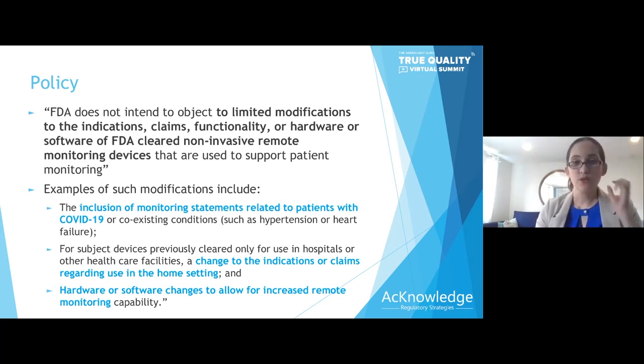If the subject device is previously cleared and only for hospital use, FDA is also interested in allowing—again, they do not intend to object—if you plan to change the indications for use in a home setting. This is really exciting for regulators like me, because if you know what it takes to get a home use device approved, you'll know this was a big thing for FDA to include, since going from a hospital-prescription-only device to a home-use device usually requires a lot of testing and would absolutely need a 510K. But when looking at the benefit-risk ratio of these types of devices, the benefit absolutely outweighs the risk here, and that's captured within this guidance document.